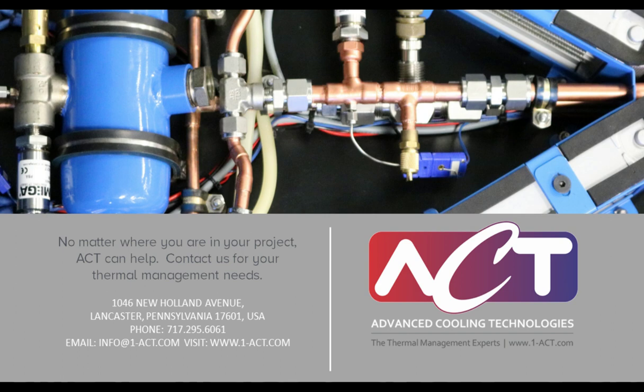Thank you. How does gravity affect the boiling process? It's an interesting question. Gravity plays an important role in two-phase systems at both the evaporator and the condenser portion. We all know, from watching a pot boil on our stove, that the vapor naturally wants to rise to the top from buoyancy forces. It's the bubbles you see rising to the top of your pot on the stove. So the same thing happens in a pumped two-phase system. The vapor naturally wants to go up, and liquid naturally wants to go down. So we often try to design pumped two-phase systems to benefit from gravity in any way that we can. We have the condensers positioned physically above the evaporators if at all possible, and we have the inlets and outlets positioned such that gravity is always providing a benefit. That's not an absolute requirement of a pumped two-phase system. They can work against gravity if needed. It just needs to be designed around that.